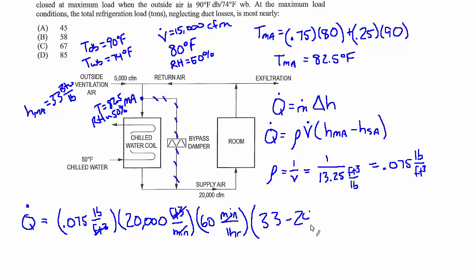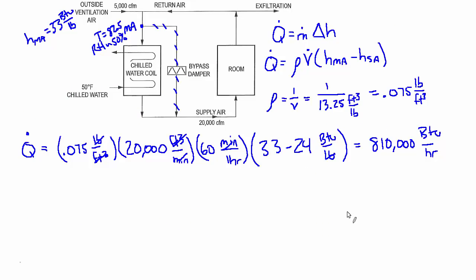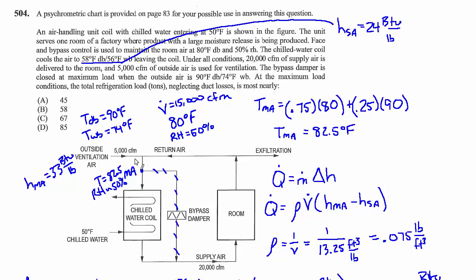33 minus 24, and that has units of BTU per pound. That gets rid of pounds, so we should be left with BTU per hour, and that's 810,000 BTU per hour. They asked for the answer in tons, so to convert that to tons we have to divide it by 12,000 BTU per hour per ton. BTU per hour goes away, we're left with tons. Q̇ equals 67.5 tons, pretty close to answer choice C.